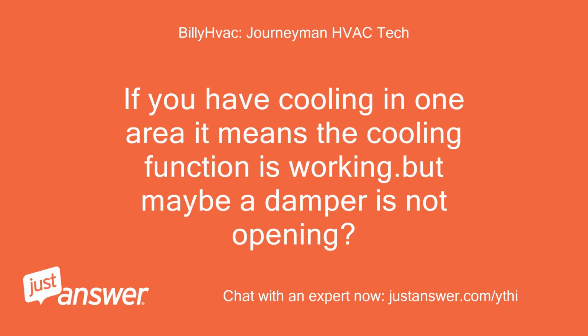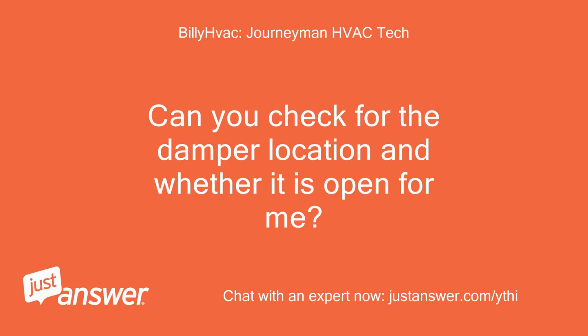If you have cooling in one area, it means the cooling function is working. But maybe a damper is not opening. Can you check for the damper location and whether it is open for me?